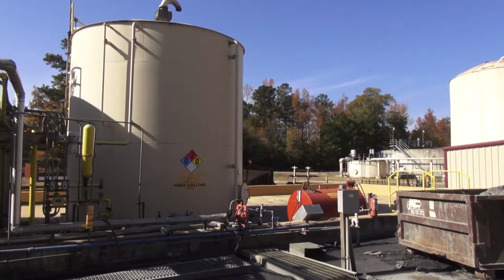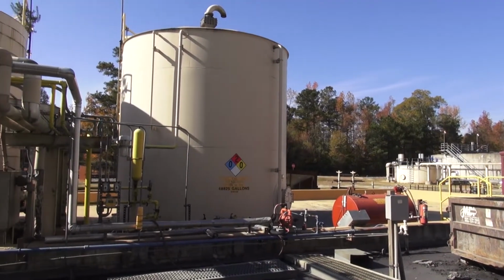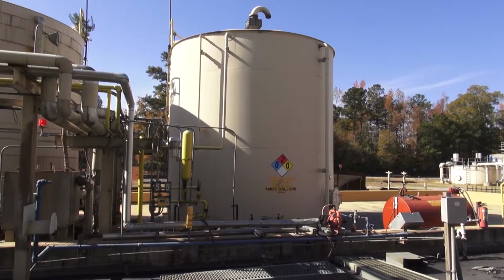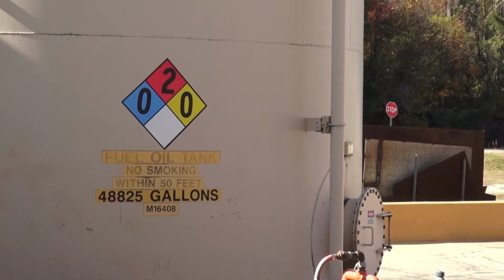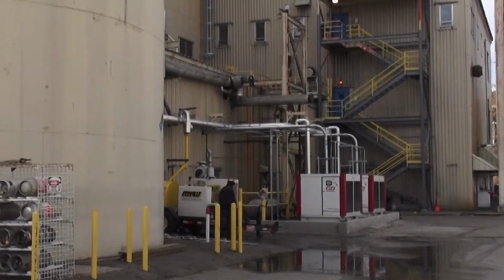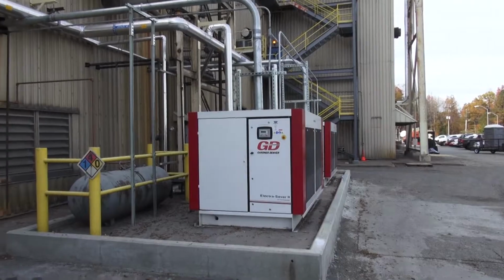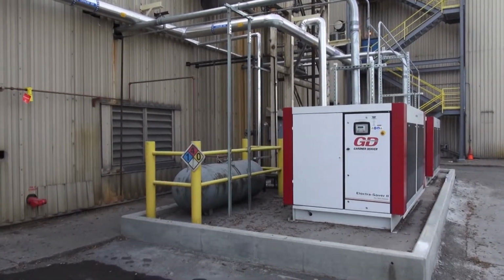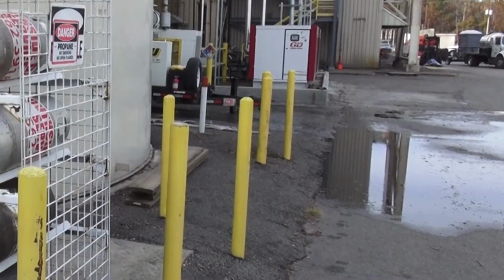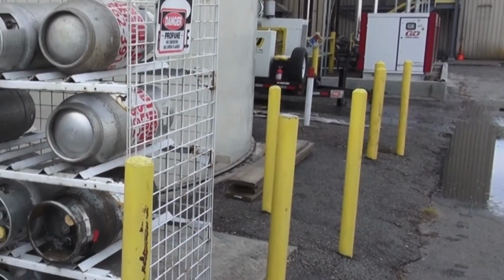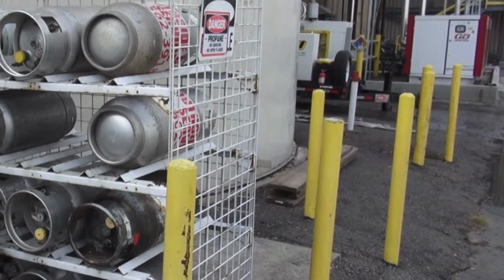There's a 48,825-gallon tank on the west side of the plant that contains number 2 fuel oil. Our plant uses number 2 fuel oil as a fuel source. There's 1 propane tank and a propane tank storage rack at the facility, which are located next to the water tank across from the cooling tower. If you suspect a propane leak, no matter how small, immediately stop all work in that area and notify the control room.